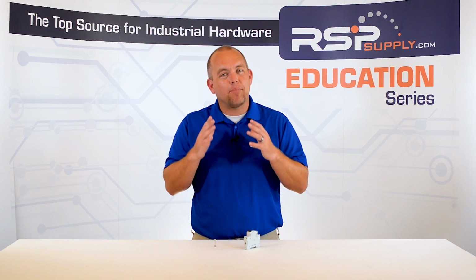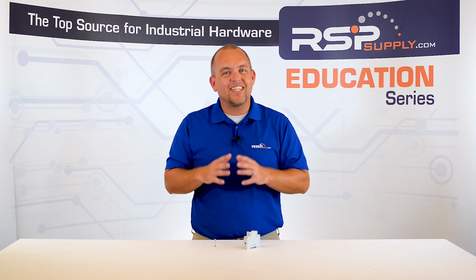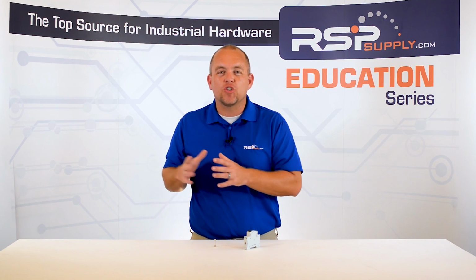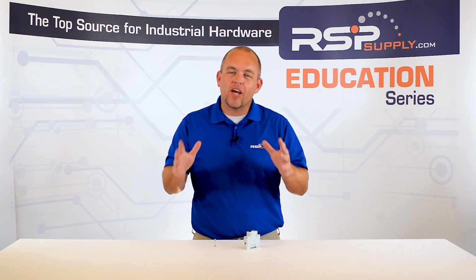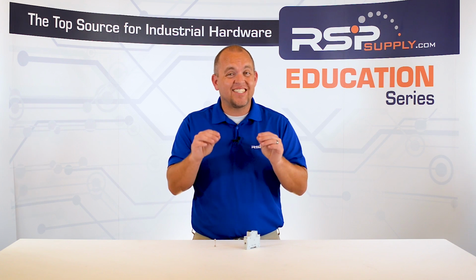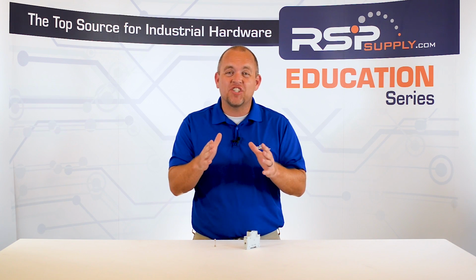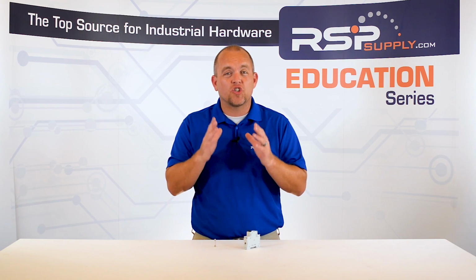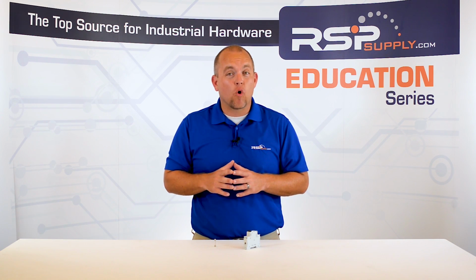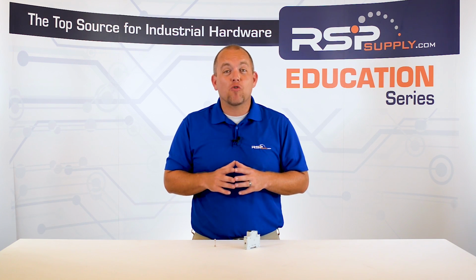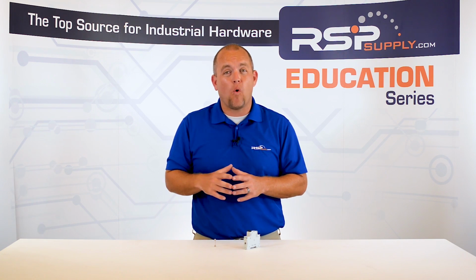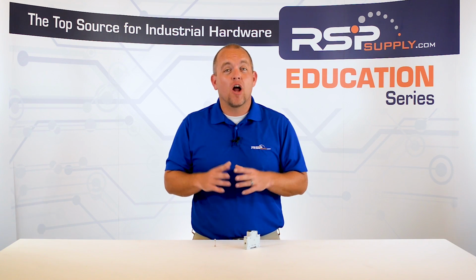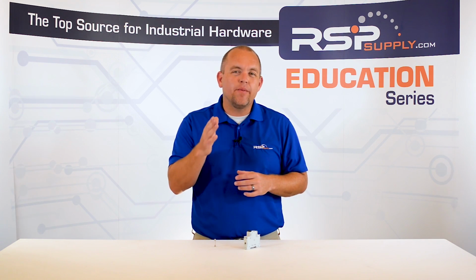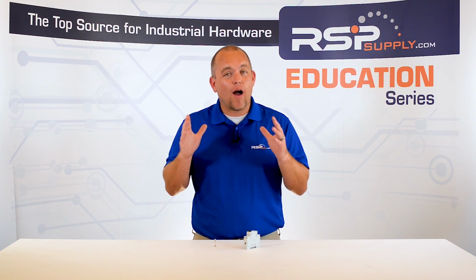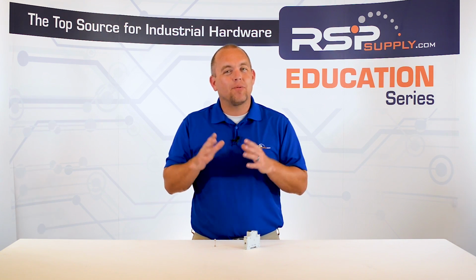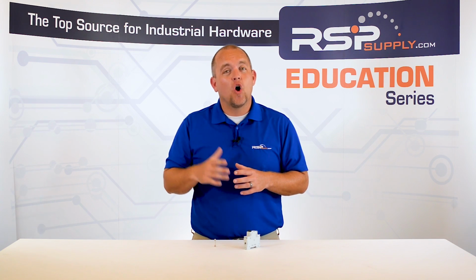So depending on the application you may encounter, it will largely dictate which device will be better suited for your specific needs. But as a general rule, fuses are more simplistic and reliable. They cost less initially and are better suited for individual circuit protection, but can create more cost over time with each use and create hazards due to the exposed connection points. Whereas circuit breakers offer better branch circuit protection and do not need to be replaced after each use. They are, however, more expensive initially, and because of their complexity, are more prone to failure over time.